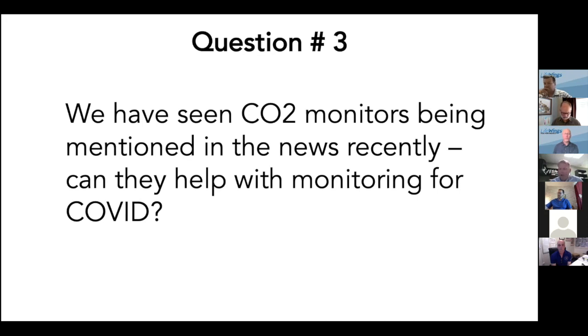CO2 monitors are a good indicator of the amount of ventilation air, because essentially what you're measuring—ambient CO2 is in the 400 to 600 parts per million range, depending on where you're at in the country. But I've seen classrooms up to 5,000 parts per million, because there is no outside air in the classroom and the classroom is fully loaded.